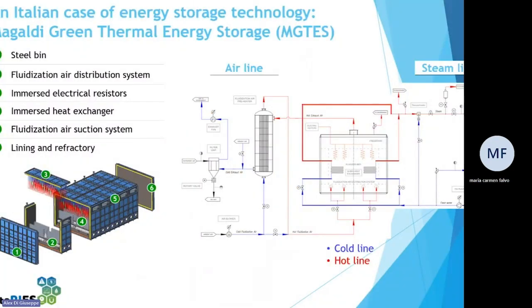Starting from the name, MGTES stands for Magaldi Green Thermal Energy Storage. MGTES is a sensible heat thermal storage. In fact, it uses simple silica sand to store the energy in the form of high temperature heat. As you can see in the bottom of the picture, the MGTES is represented as a simple receiver, a simple container that includes silica sand in which active elements for the charging and discharging phase are immersed. In particular, with the number 3, you can find electrical resistors that are immersed directly in the sand to charge the system. And with number 4, the immersed heat exchanger for the discharge of power. The receiver is thermally insulated to reduce the thermal losses through the exterior to a minimum.